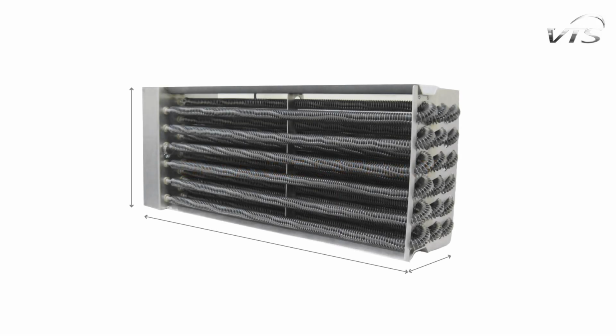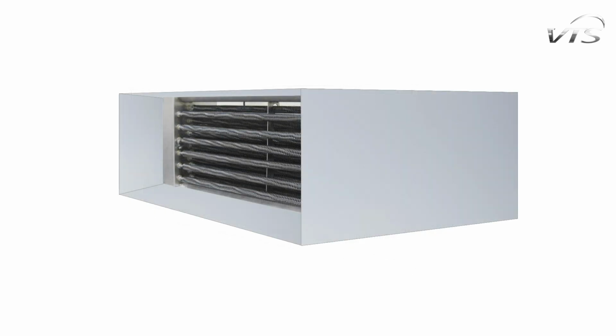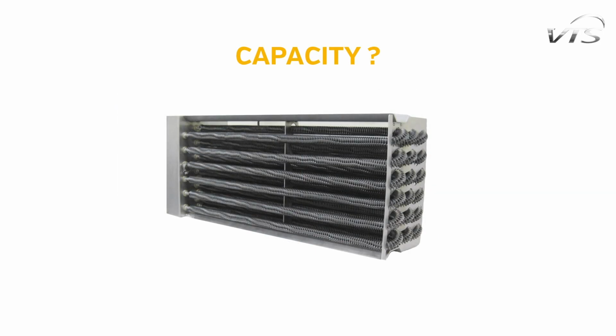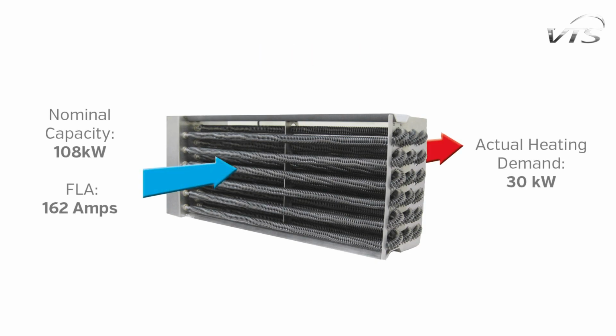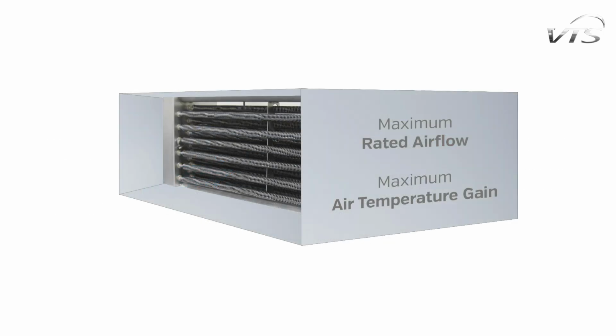Typically, electric heaters are sized to the air handling units in terms of their physical dimensions. They are simply fitted to the cross-section of the unit so they can be easily accommodated inside. But what about the performance of the heater in relation to the actually required heating capacity? In the field of capacity, electric heaters are usually strongly oversized to the actual needed heating demand. Why? Simply because they are always designed for a certain size of air handling unit, assuming its maximum airflow rate together with its maximum air temperature gain.